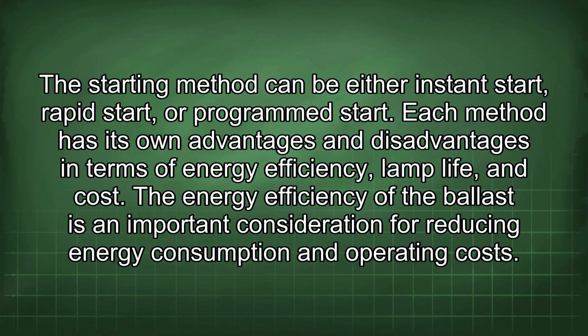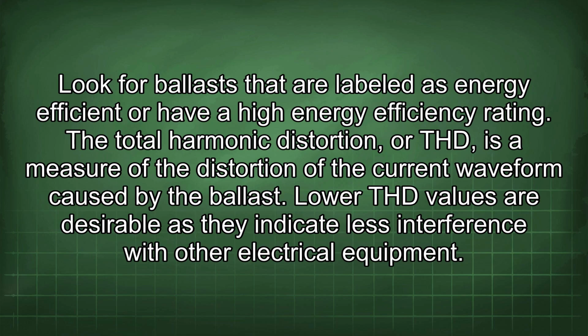The energy efficiency of the ballast is an important consideration for reducing energy consumption and operating costs. Look for ballasts that are labeled as energy efficient or have a high energy efficiency rating. The total harmonic distortion, or THD, is a measure of the distortion of the current waveform caused by the ballast. Lower THD values are desirable as they indicate less interference with other electrical equipment.